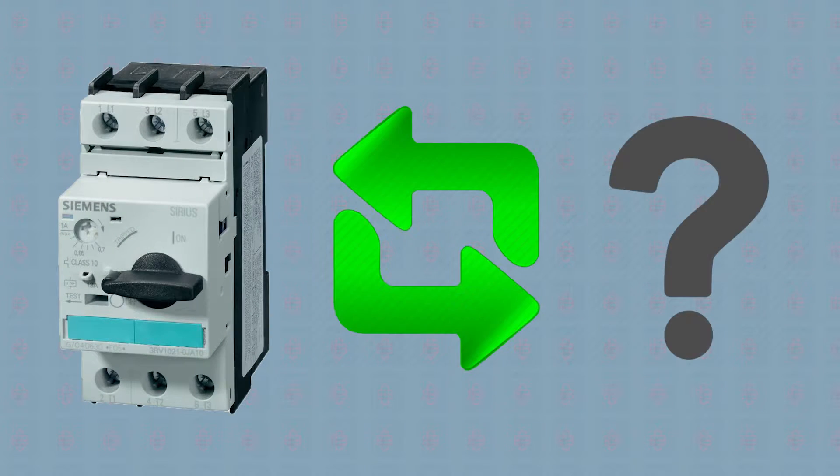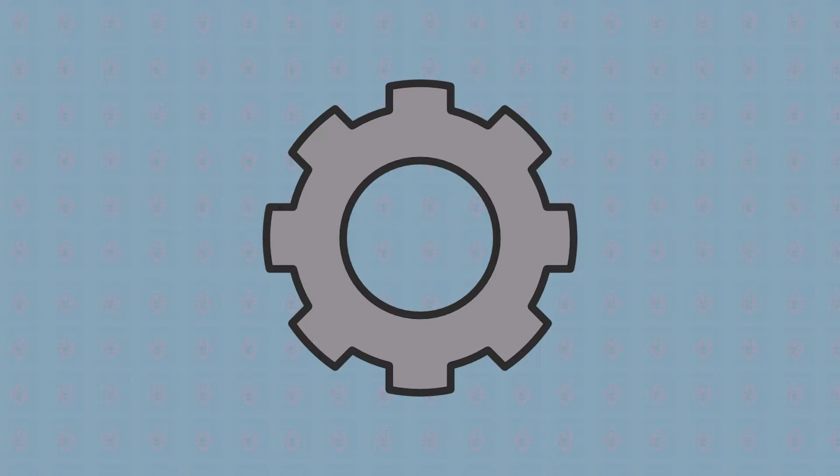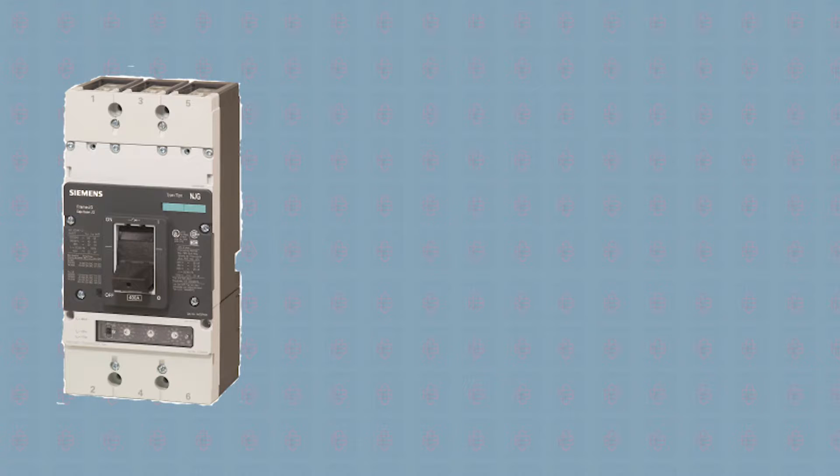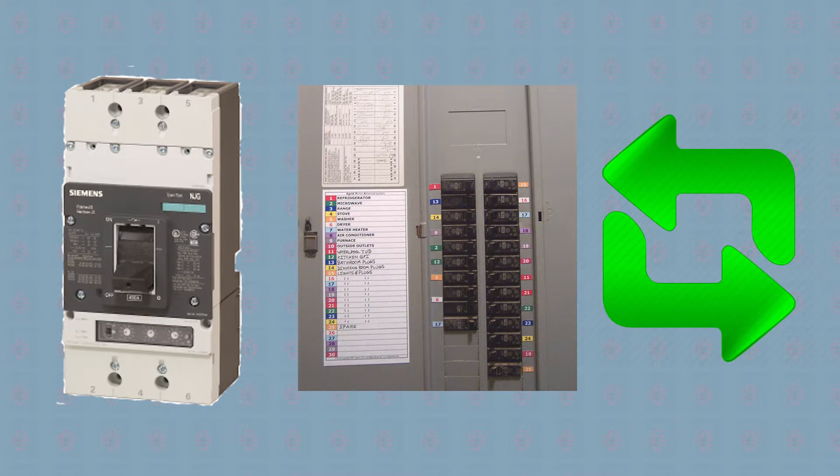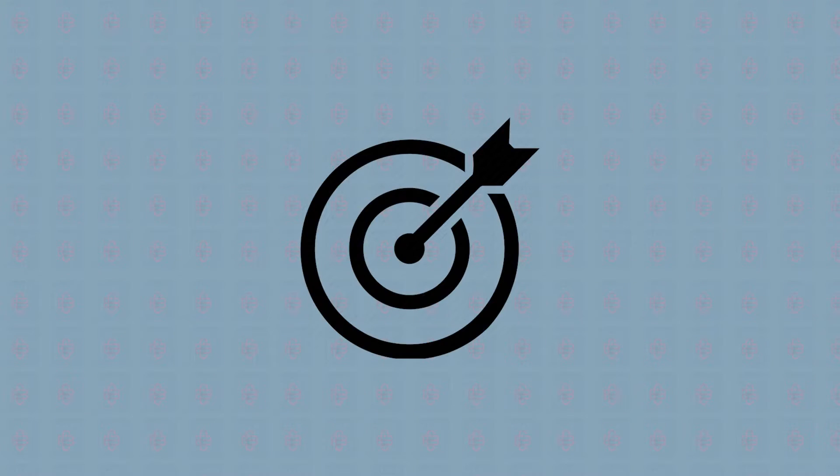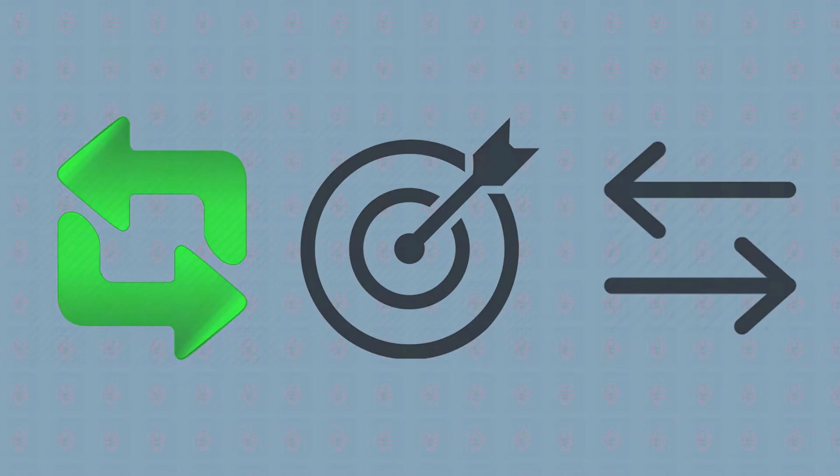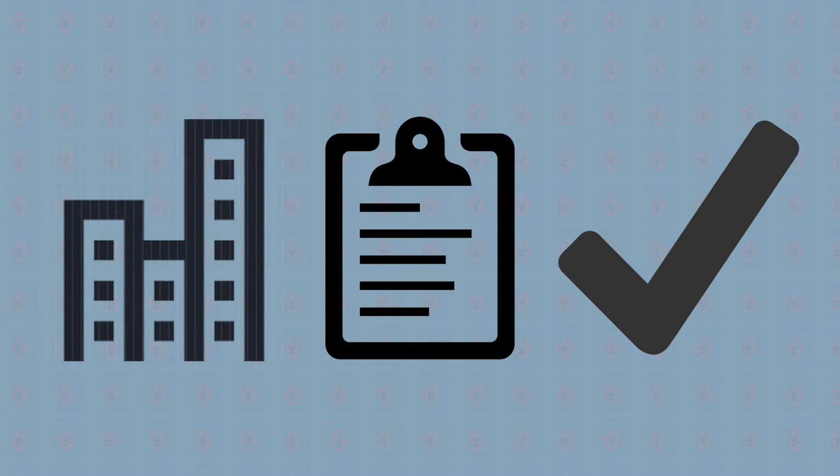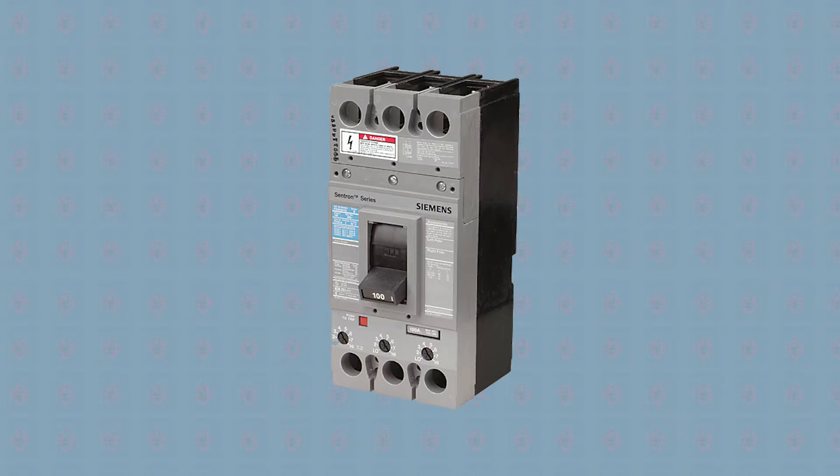That's a great question. Unfortunately, there isn't a simple answer. The purpose, construction, and function of circuit breakers and panels themselves dictate interchangeability, as well as national codes and regulations. Accurately replacing or interchanging a circuit breaker will keep buildings up to code, maintain service listing approval, and even save lives. Interchangeability starts with the structure of the breakers themselves. Important characteristics of a circuit breaker include voltage, single or double pole, amperage, mounting style, ground or arc fault protection, and more.